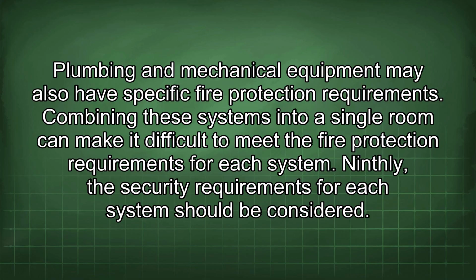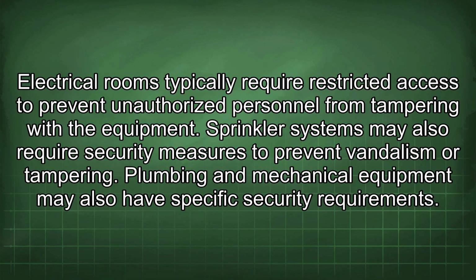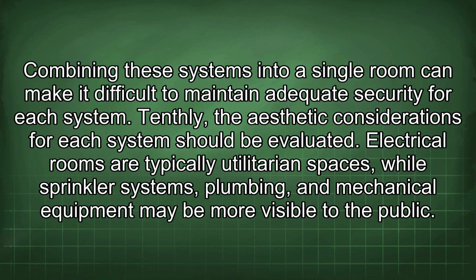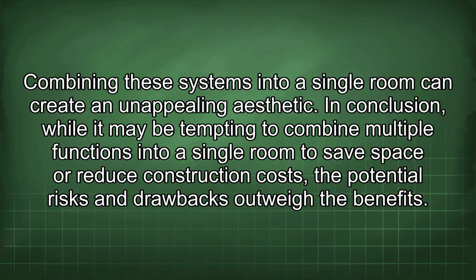Ninthly, the security requirements for each system should be considered. Electrical rooms typically require restricted access to prevent unauthorized personnel from tampering with the equipment. Sprinkler systems may also require security measures to prevent vandalism or tampering. Plumbing and mechanical equipment may also have specific security requirements. Combining these systems into a single room can make it difficult to maintain adequate security for each system. Tenthly, the aesthetic considerations for each system should be evaluated. Electrical rooms are typically utilitarian spaces, while sprinkler systems, plumbing, and mechanical equipment may be more visible to the public. Combining these systems into a single room can create an unappealing aesthetic.